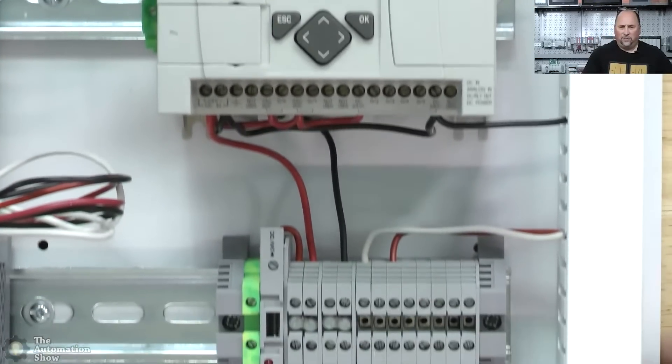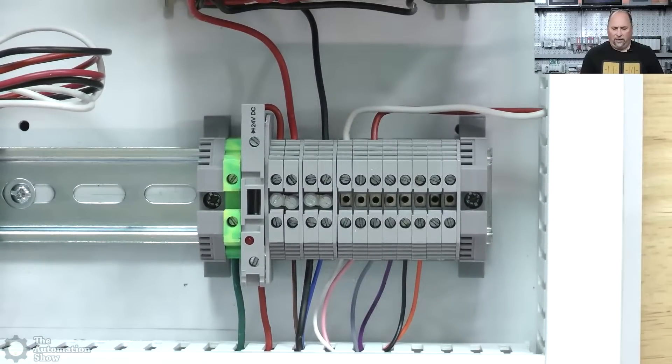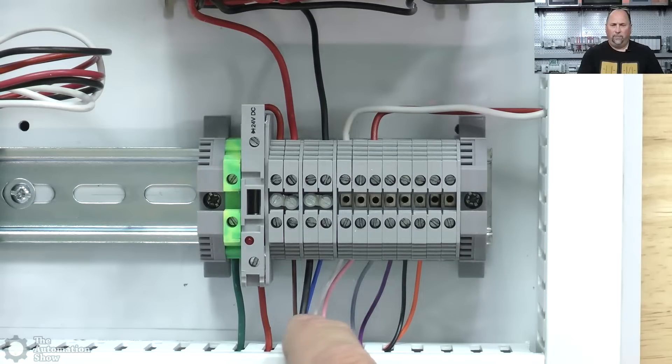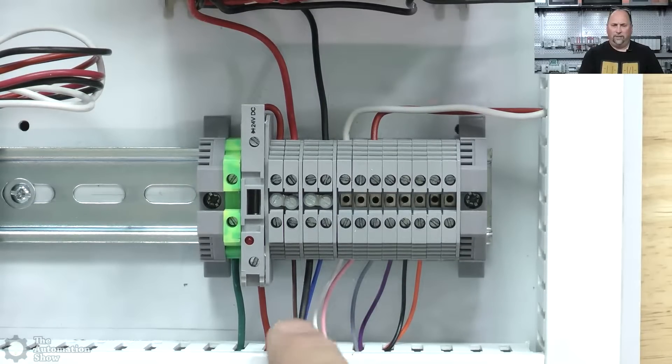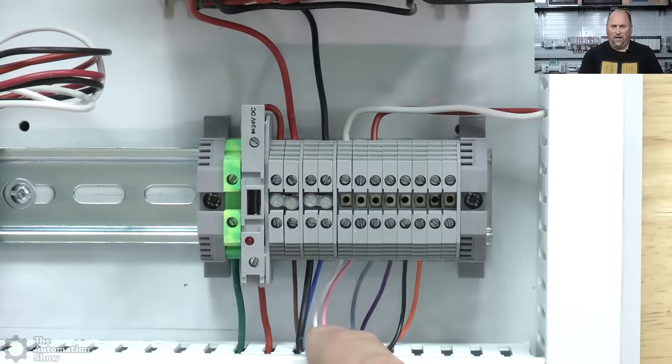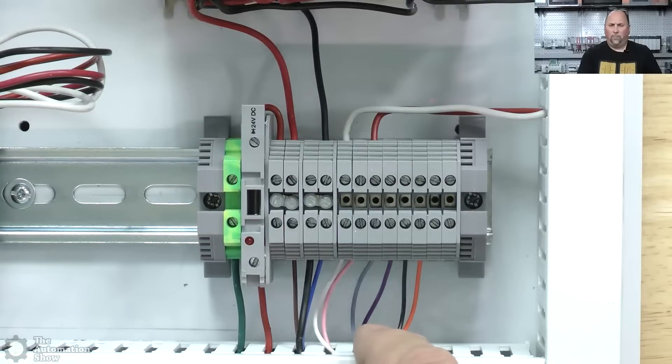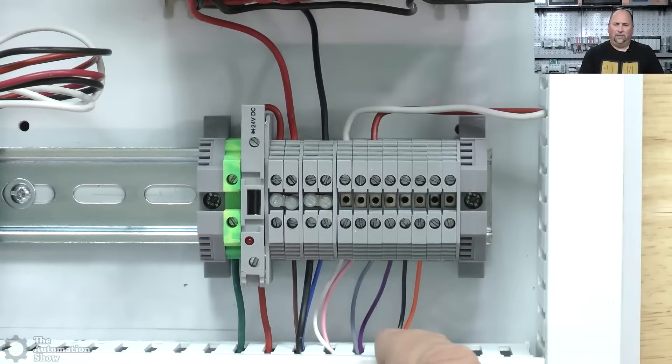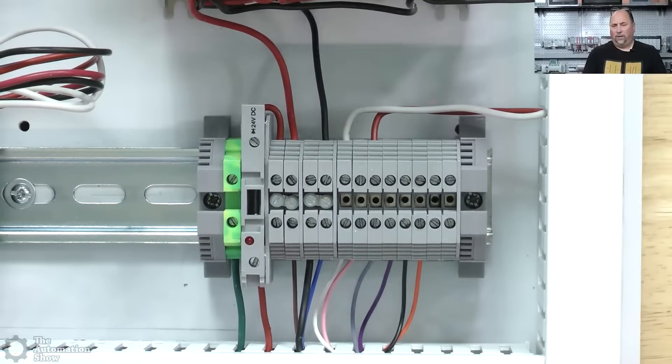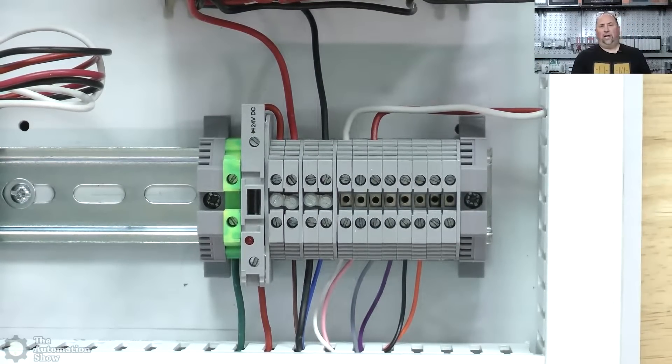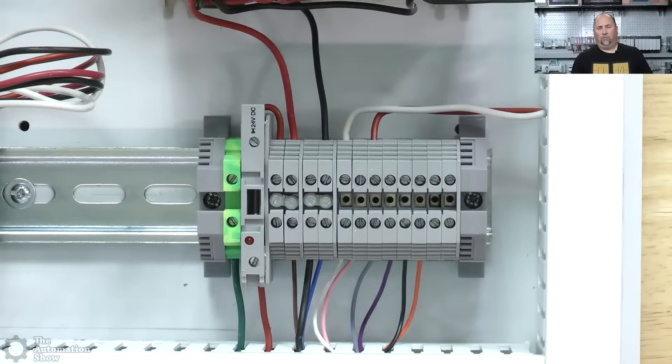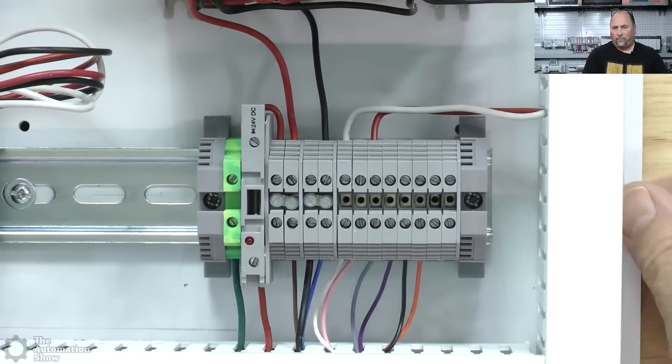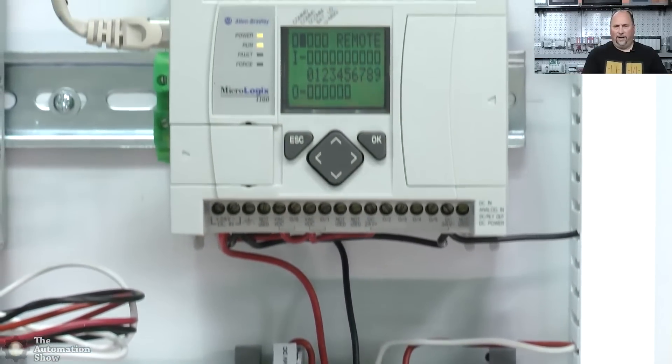So first we'll start down here. Here you can see I got the brown and the blue coming in the plus and minus, and then you can see the white that's A and the pink is A-naught. The gray is B and the purple is B-naught. The black is Z and the orange is Z-naught. So I'm only using the A and B with the MicroLogix 1100.